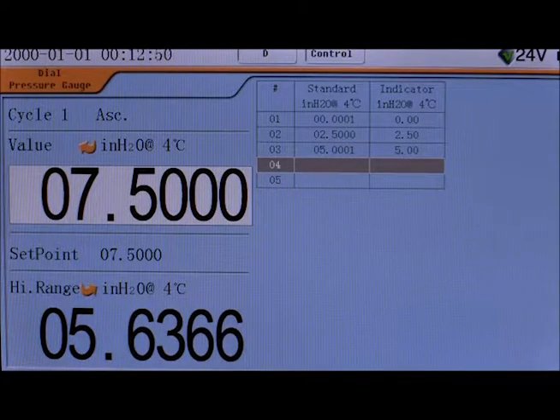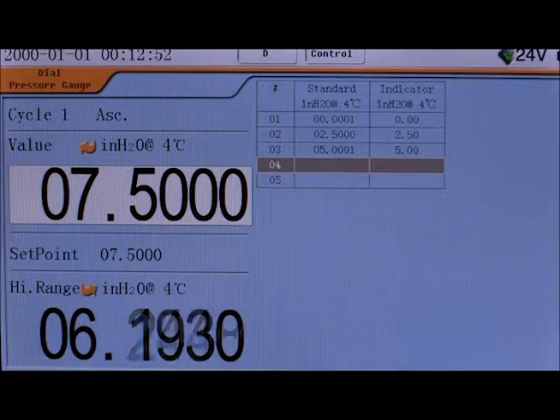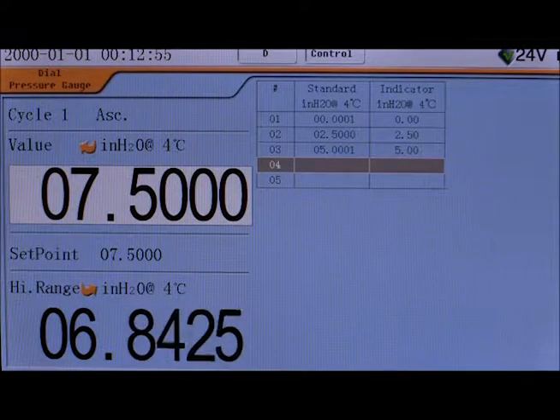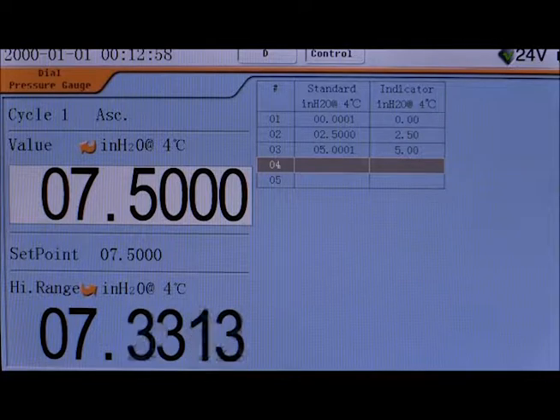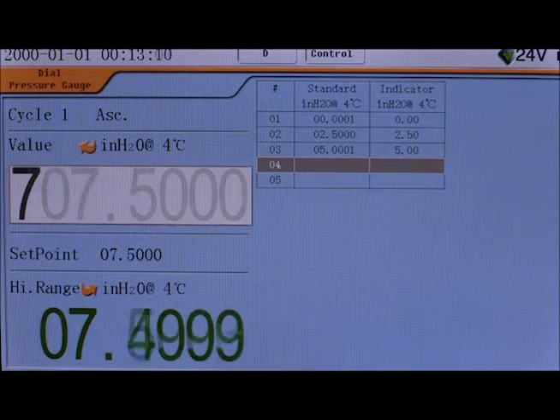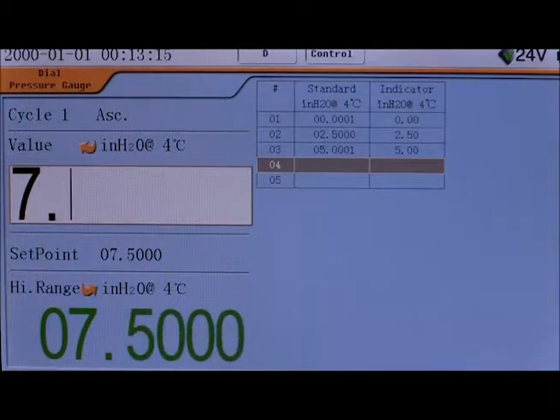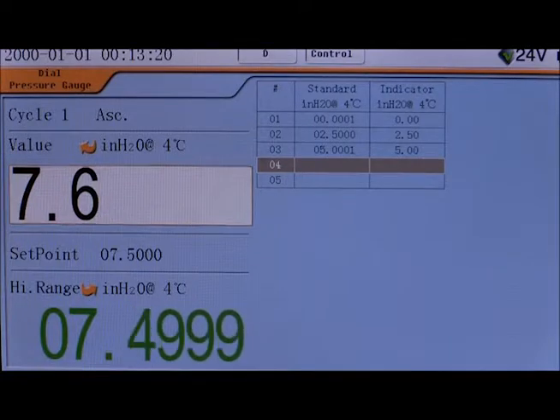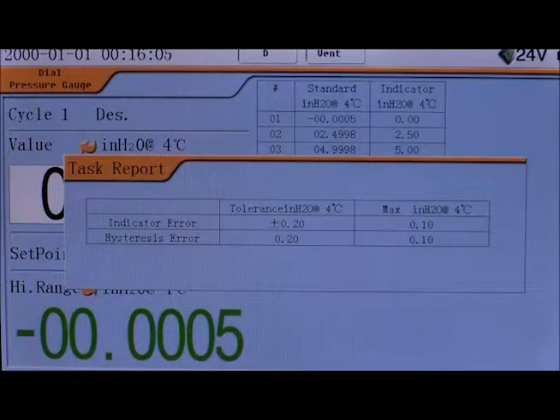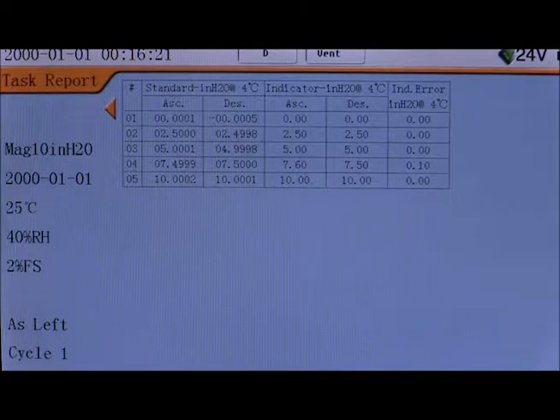The 761 is set up to default the DUT readings to the set point pressures. This allows you to make micro adjustments with the 761 to adjust to the cardinal point and press enter when the cardinal point is achieved. Of course, manual entries of the DUT can also be put in if that is the preferred method of processing the results. Once the test is complete, the results will be displayed with the choice to record the results as found or as left. Any results that are out of tolerance are colored red. In this case, my gauge is in tolerance, so I'll record the results as left.